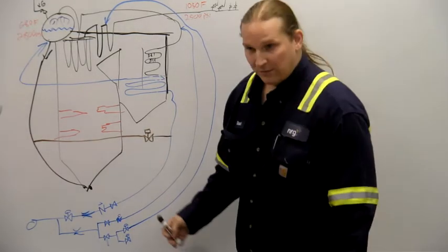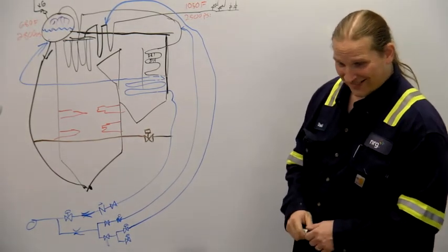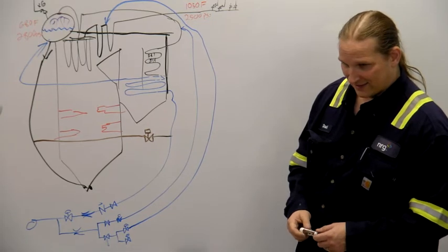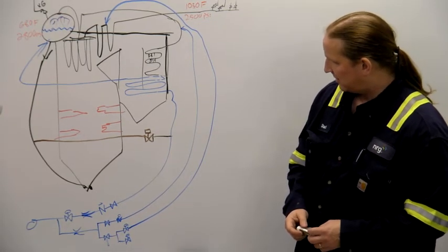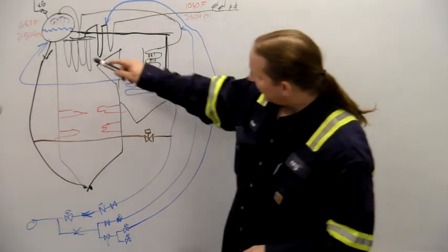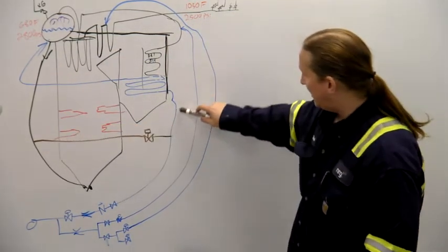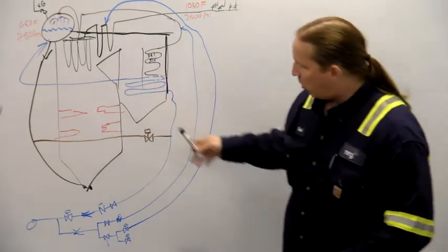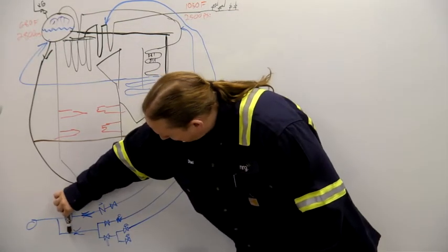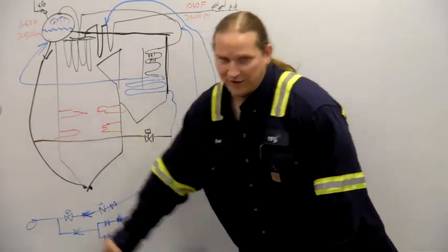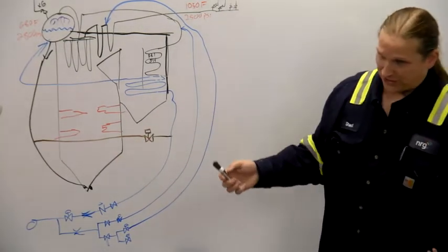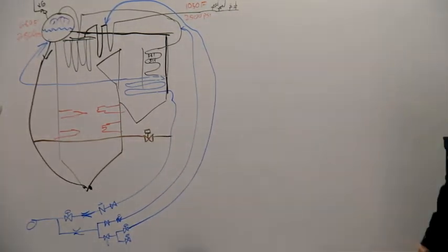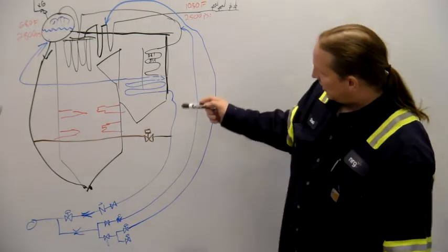So the water is not going from pump to recirc, it's actually going from the downcomer to recirc. Right, it is the downcomer recirculating into the economizer when the 142 valve, the level control valve, is shut. If the pump's open, then it short circuits and goes the other way. But that's not its purpose. That's something that happens.